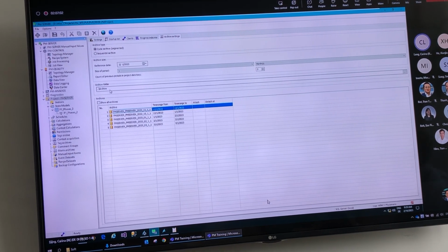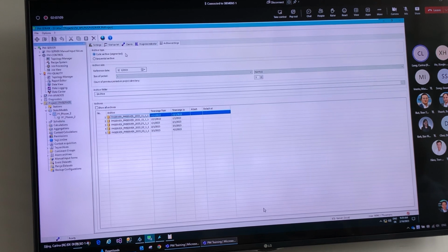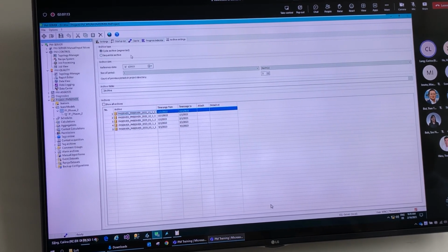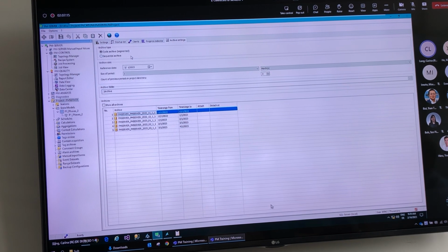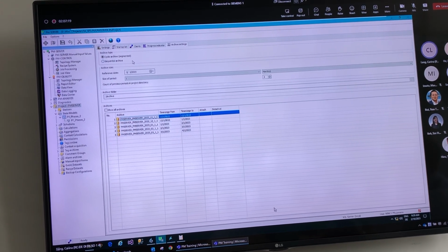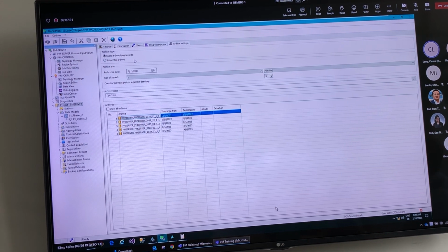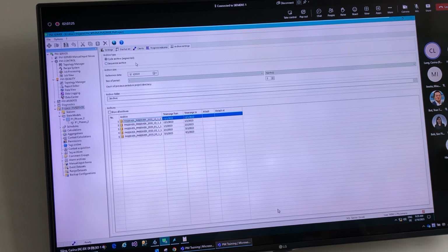So that means in the cyclic archive, the oldest archive, which is out of the range we have configured here, will be deleted, and in the sequential archive, we just detach this archive and store it somewhere else. So if we will need this data again, then we can attach it again so that we get access.